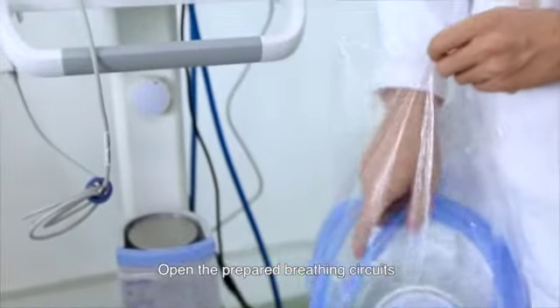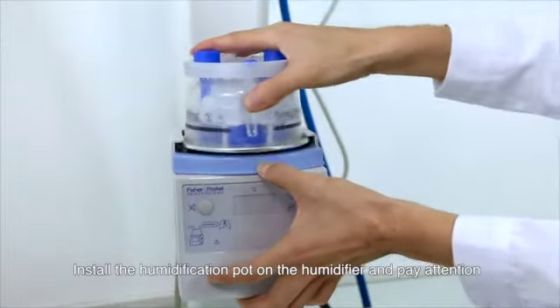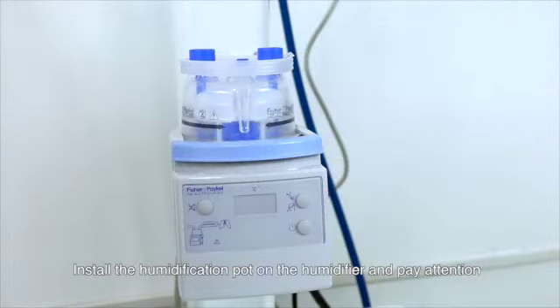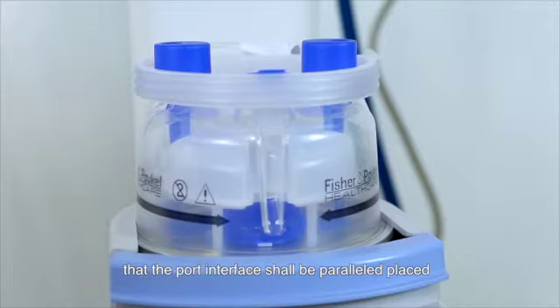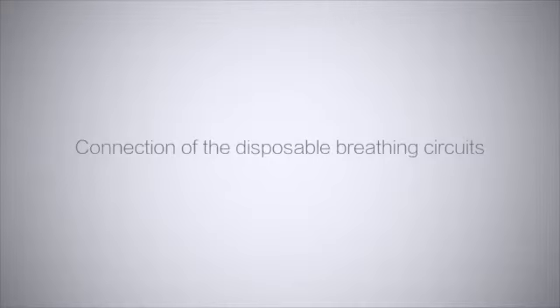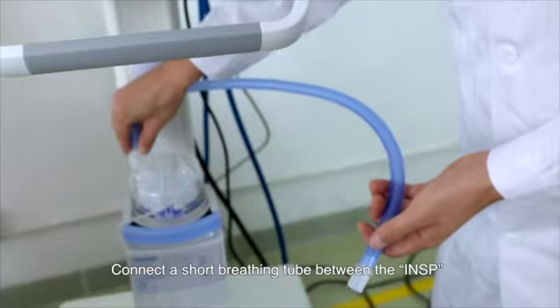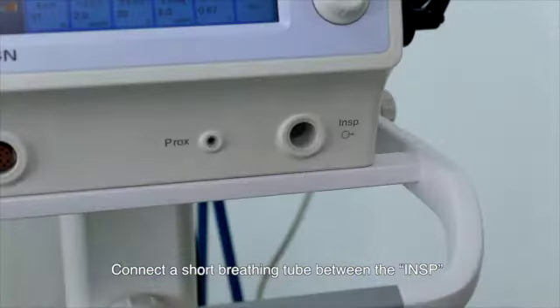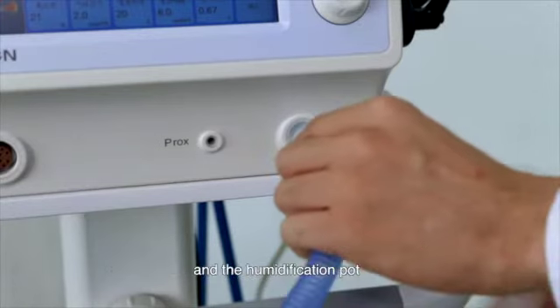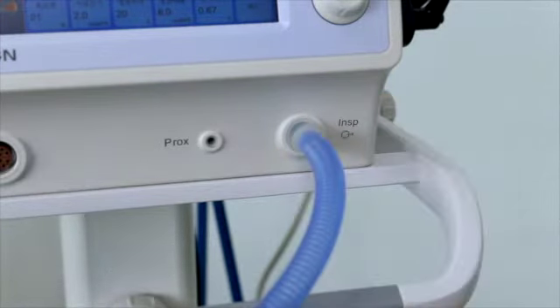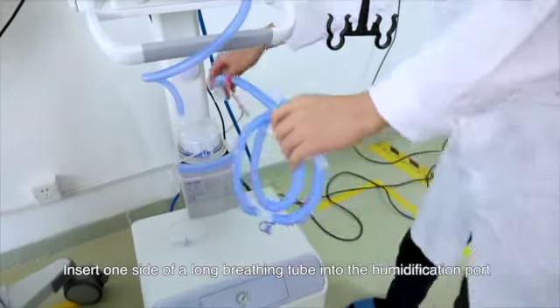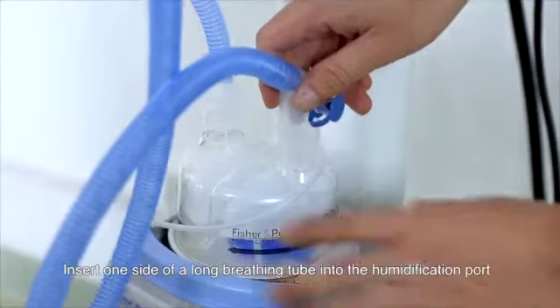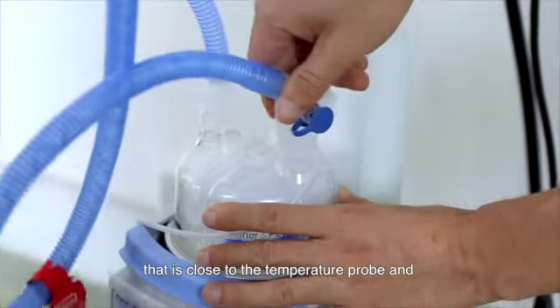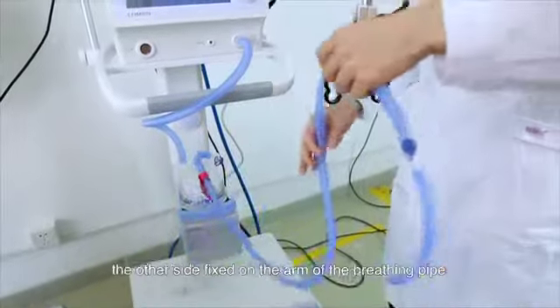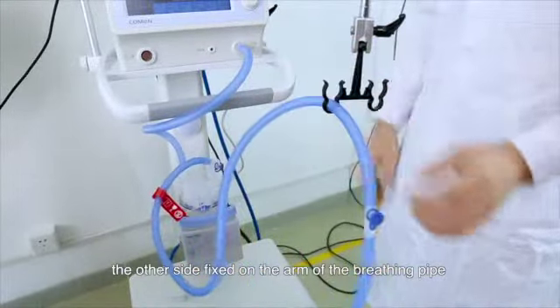Open the prepared breathing circuits. Install the humidification pot on the humidifier and pay attention that the port interface should be placed parallel. Connect a short breathing tube between the INSP and the humidification pot. Insert one side of a long breathing tube into the humidification port that is close to the temperature probe and fix the other side on the arm of the breathing pipe.